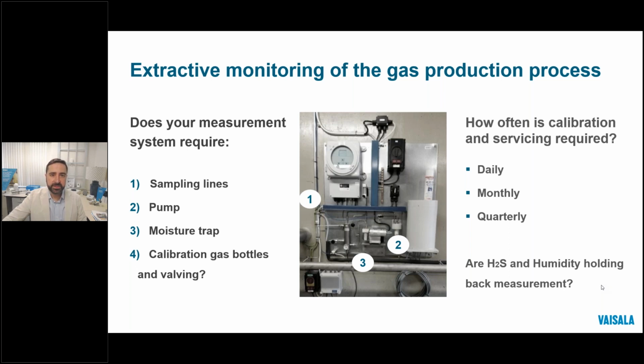Additionally, the types of sensors used in these systems and in GCs require frequent calibration, typically ranging from daily to quarterly. There are also some that rely on fresh air to perform periodic zero calibrations, but they don't account for seasonal changes in ambient air, drift from other internal sensor components, or the enclosure they might be in. So with all of that, it's common to see a looser accuracy and stability specification from some of these options. Next.